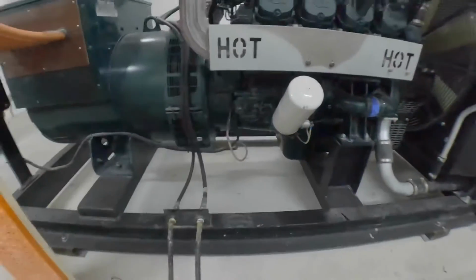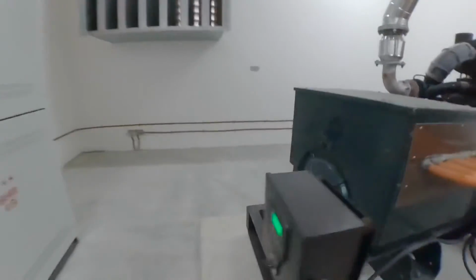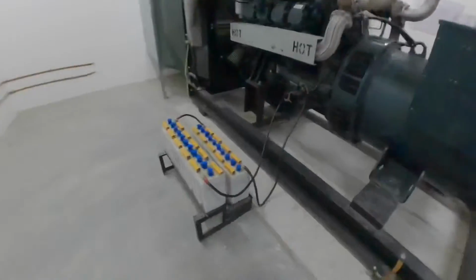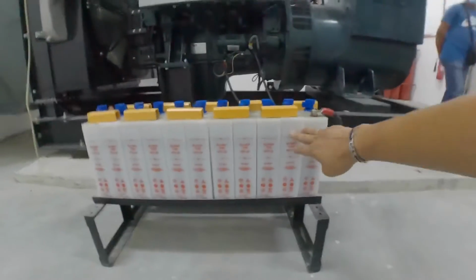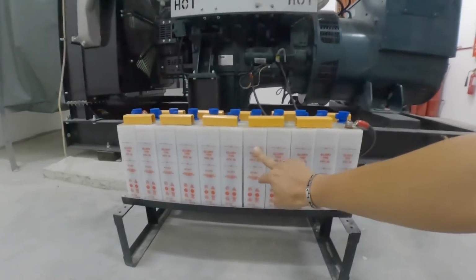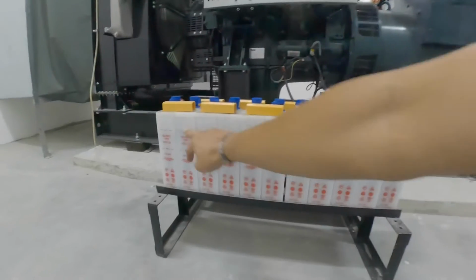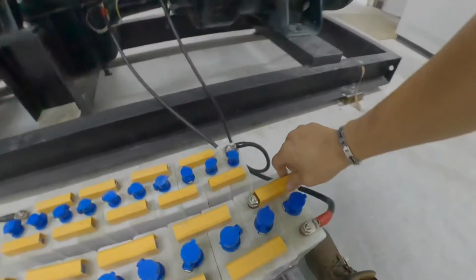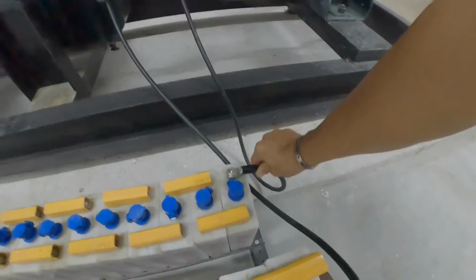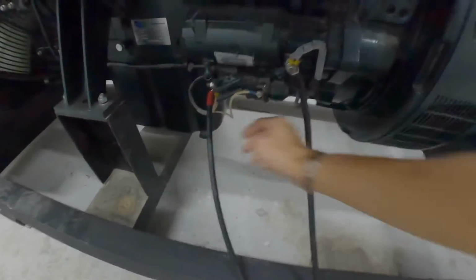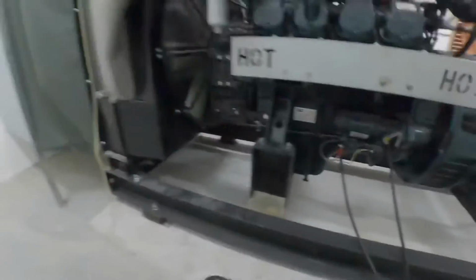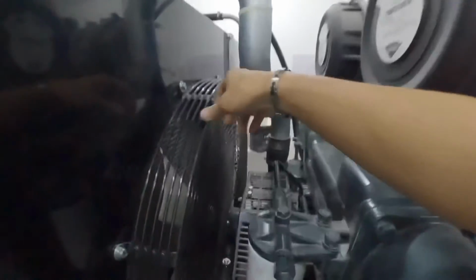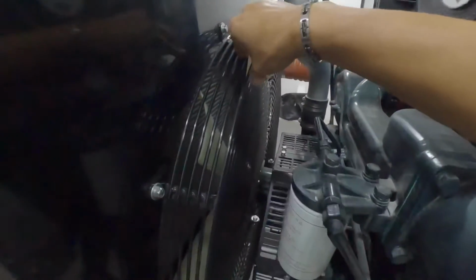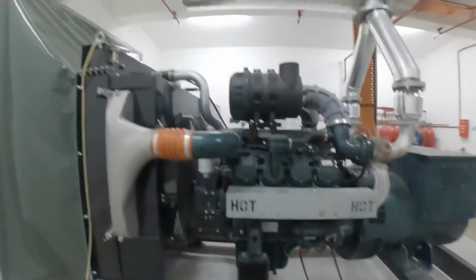Next we're going to check the genset battery. This is the genset battery. It's a nickel cad. Currently the electrolyte level is all at maximum. Termination is tightened, no corrosion on the cable. Cable is in good condition. Starter okay. Then we have this fan belt, radiator fan belt and radiator fan, no obstruction. Radiator coil looks very clean. This is a Doosan genset.